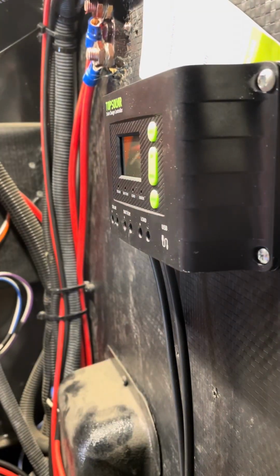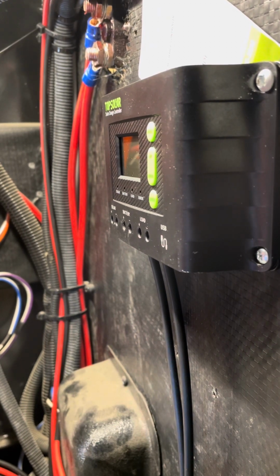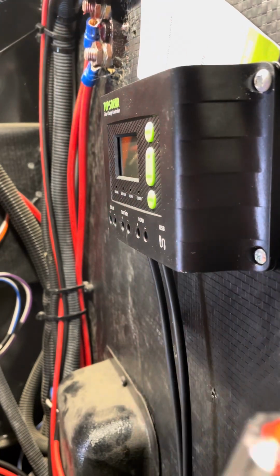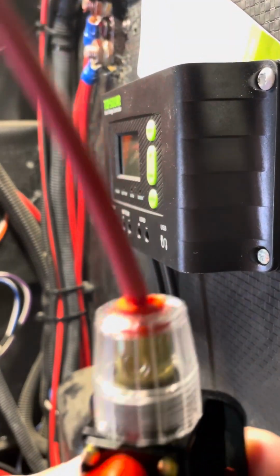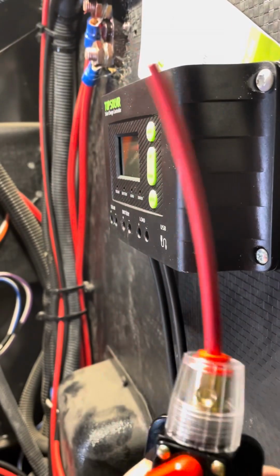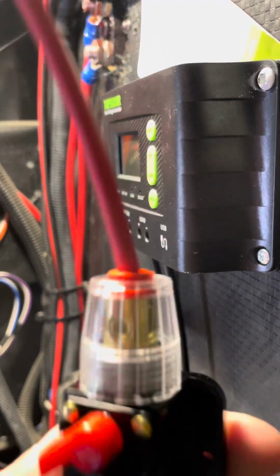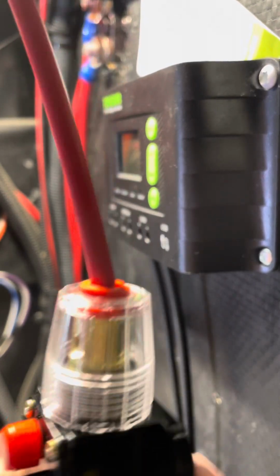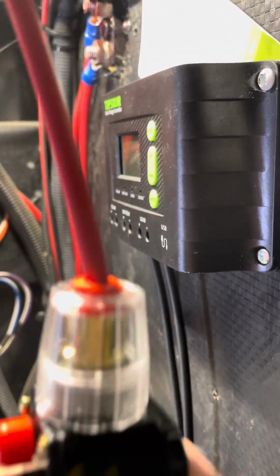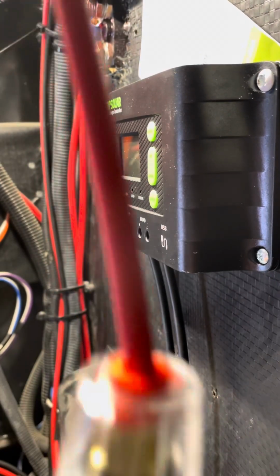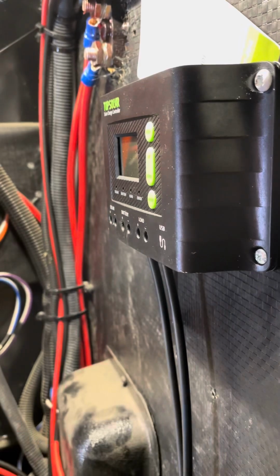With the fuses removed, now it's time to install the circuit breakers. I have pre-installed the wire between the circuit breaker and the control panel for both circuit breakers. I will install those, leave them loose, and then connect the wire from the battery to one circuit breaker and from the solar panel to the other.